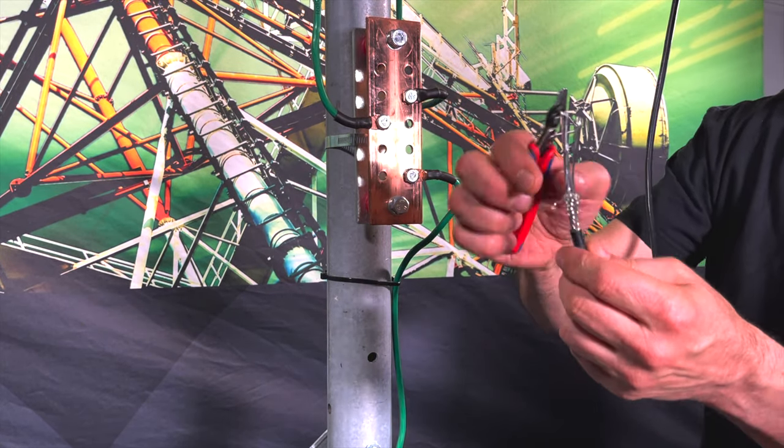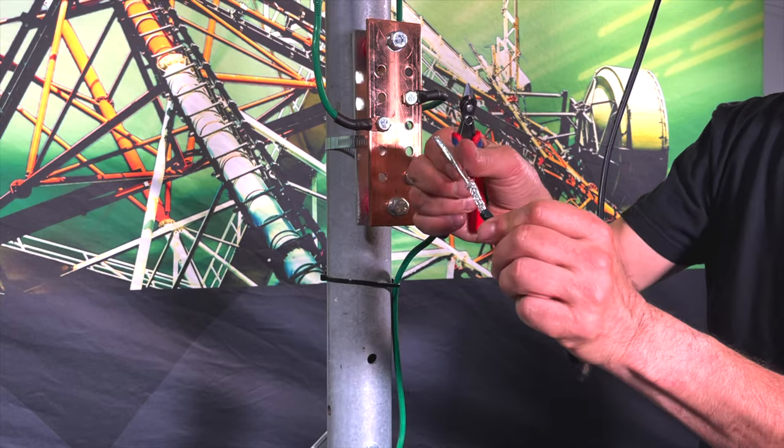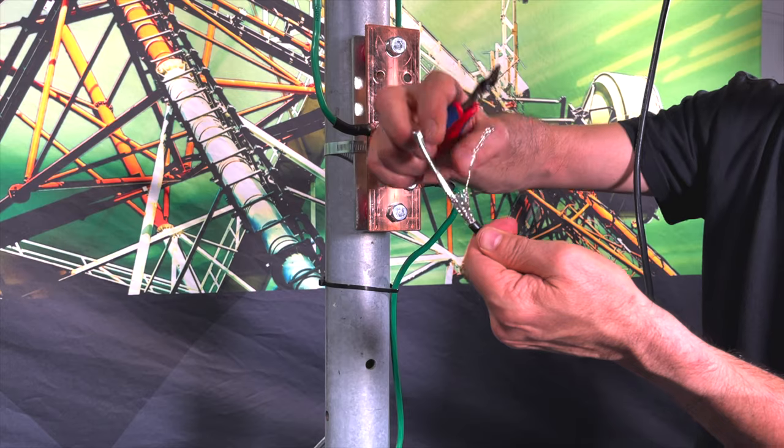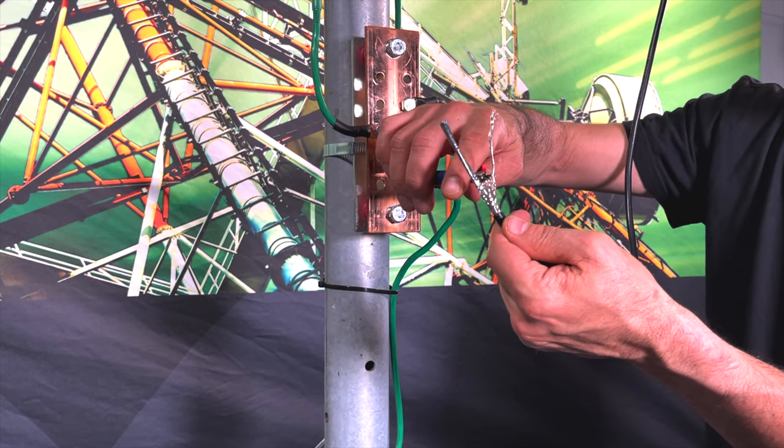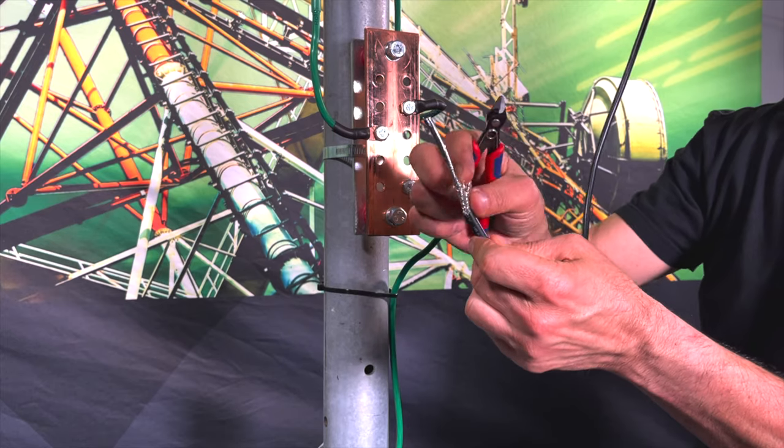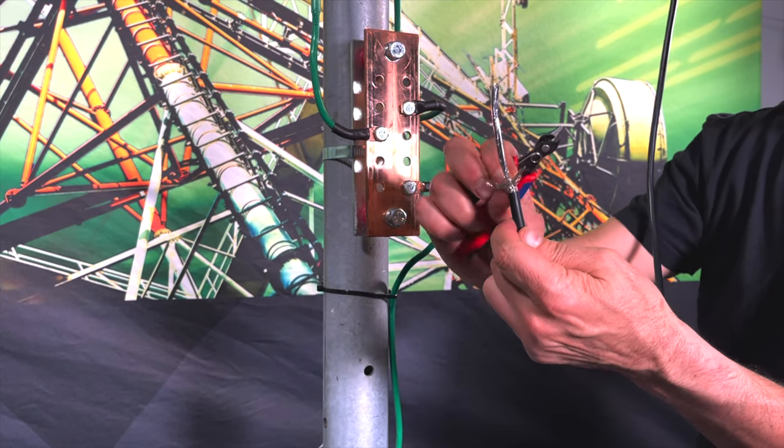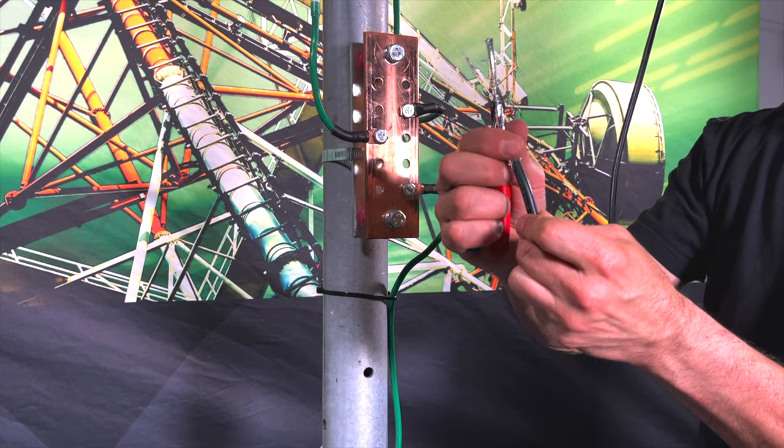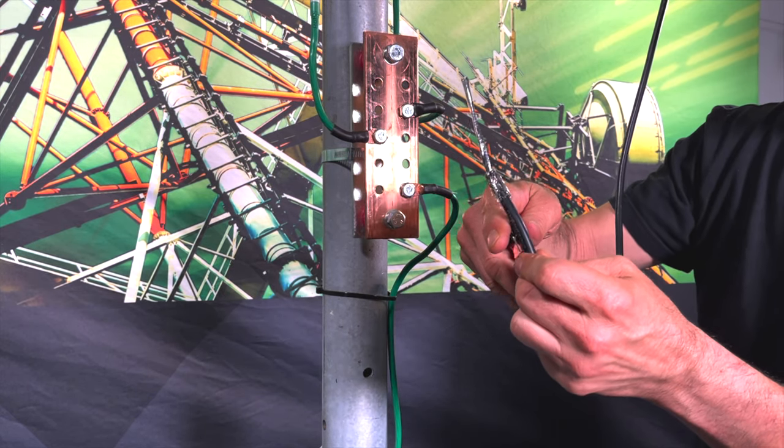Once the braid is removed, we're going to take and cut our 16 gauge ground wire to about the same length, about one inch of that will be exposed. Now, what we're going to do is fold all of this backwards over the jacket of the cable, so it's pulled back. We'll clean this up a little bit.